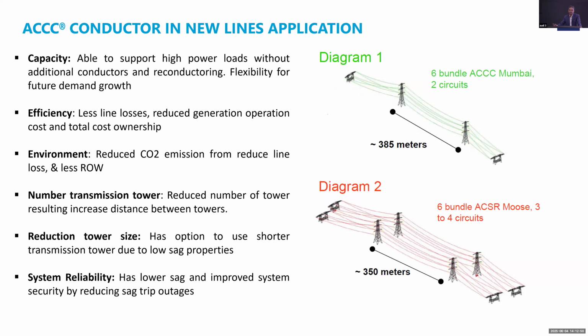One is it can future-proof a new transmission line, a new transmission corridor, right? By giving double the capacity from the beginning. The original way of planning a transmission system is no more applicable, is not as easy to do as what we used to do before. Today, we have so many injection points coming into a grid system, right? Especially because of renewables. Last time, you would exactly know where to put your coal plant. You know exactly where to put your gas plant. But with renewables, it would be multiple entries. So what's happening is you cannot plan the capacity of a certain transmission corridor upfront exactly 100%. So you need this additional capacity, and HTLS conductors are able to give you this additional capacity.